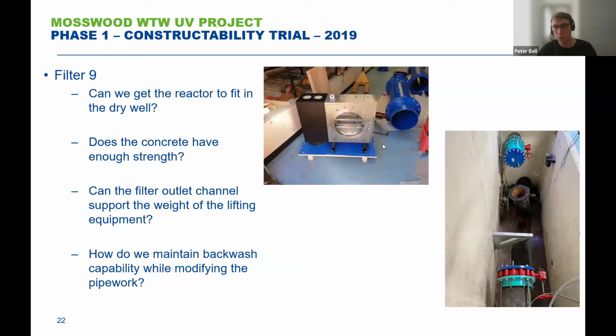The way the filter backwashing works is it's on a large ring main fed from a header tank. And it is cross-connected at the sort of top end of the ring main. But what we found was that if we were to supply filter washing on the even numbers, so that the odd numbers run down one side of the channel, which you can see to the top left-hand corner of the first picture, the other side of that channel is the even numbers. So we had to make sure that we weren't going the long way around that channel.